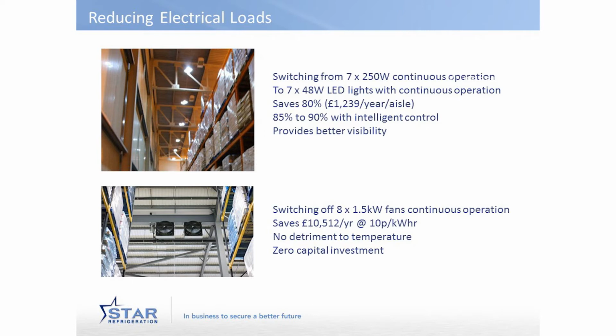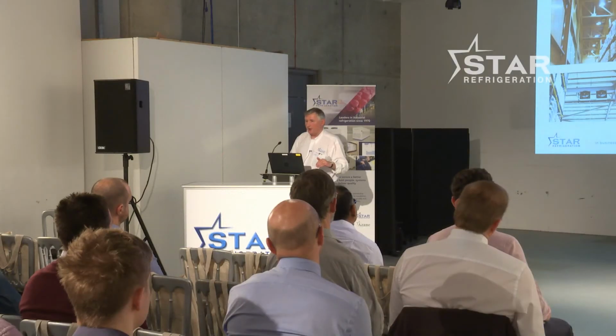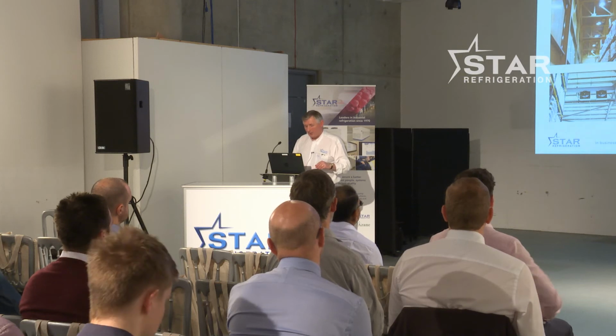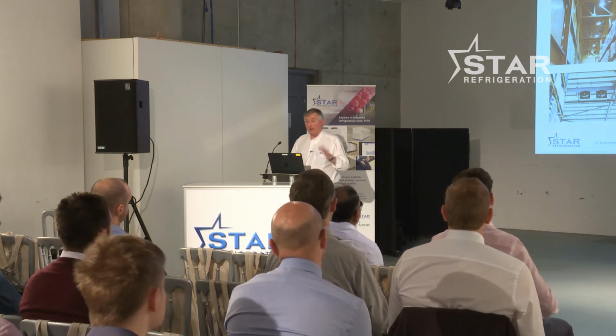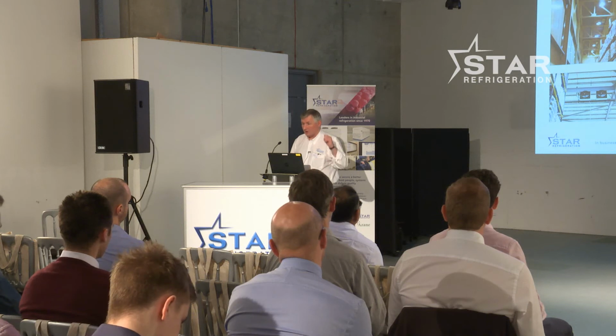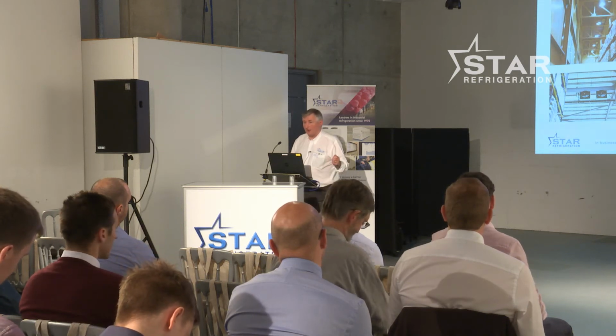The other example is booster fans within cold stores. It's quite common to see, in addition to the evaporators, there are extra fans around the room to spread the air around. But what we found is that these might be required under peak load conditions, but they don't actually need to be there operating all the time. Just by switching off the booster fans in a store, we saw no change in the temperature levels, but saved about £10,000 a year, again at 10 pence per kilowatt hour. No effect on temperature control, and in this case, zero capital investment. It was just literally turning the switch off at the times when they're not needed.